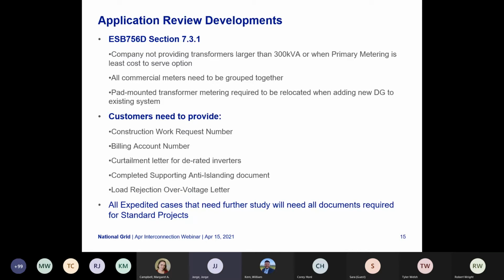Some of the application review, not really changes, but updates. So we will not be providing transformers for any standalone interconnections larger than 300 kVA. So if you have a 300 kVA system that you would like to put online, we can provide the transformer. Anything larger will require primary metering. And that also includes a 300 kVA system when primary metering is the least cost to serve option.